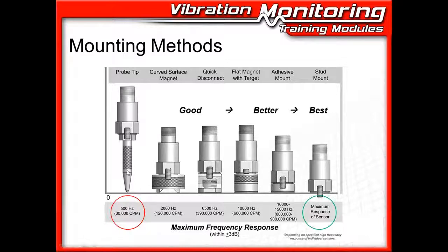So we have this chart, and I hesitate to even talk about this probe tip business, or stinger, some people might call it, or pointer. It has no real contact point, no transmission. It adds a lot of mass, and there's almost no stiffness here. So you can take a very good accelerometer and attach this probe tip to it, and all of a sudden you only have 500 hertz of frequency response. What do I see it used for that makes any sense at all? Possibly if you've got to slip by a guard or get into some real tight spot where nothing else is working for you. So generally speaking, try to avoid those unless it's a method of last resort.